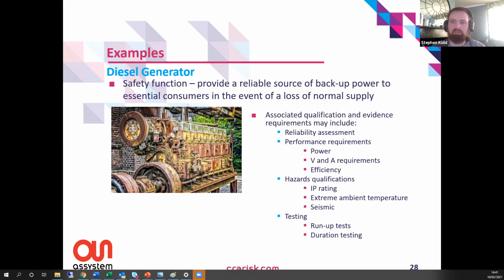There'll be performance requirements. So there'll be a specified power which needs to be delivered, which will be based on the worst case loadings from all of the essential systems in the worst case fault conditions. There'll be maybe design margin built in there as well, to give us ability for future modification, or also in case there's errors in the calculations. So we want a bit of margin in there. There may be voltage and current requirements. The output will have to be of a specific quality. We'll need to demonstrate that.